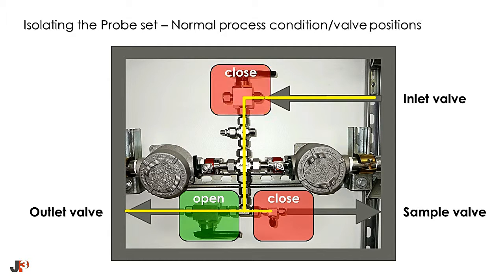To isolate the probe set, you must first close the inlet valve to stop process from entering, then close the outlet valve to stop process from exiting. Next, open the sample valve using a catch bucket to get rid of the process inside. Then close the sample valve. Let's take a better look at the entire process with the following video.